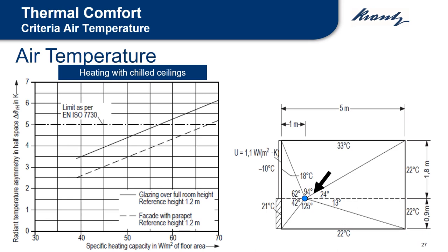The graph on the right shows the radiant temperature asymmetry in the half rooms, ceiling, floor, as a function of the specific heating capacity in watt per square meter floor area. The illustration below shows, as an example, the influence of the different room surface temperatures on the specific position of a sitting person at a height of 0.9 meter above the floor and at a distance of 1 meter to the facade.